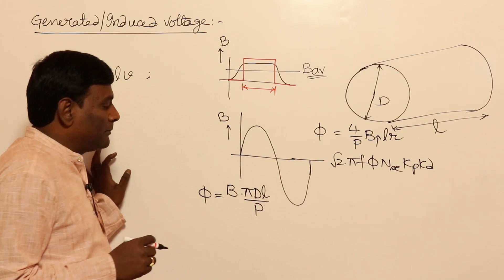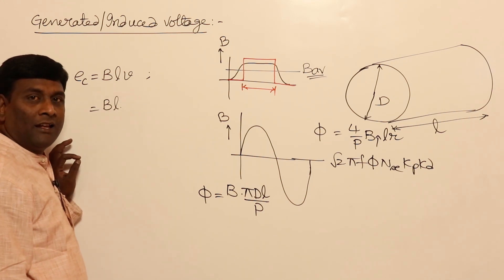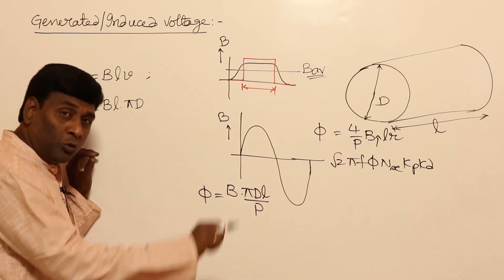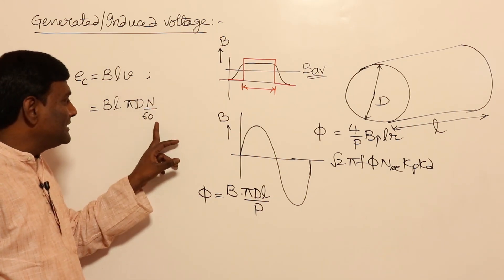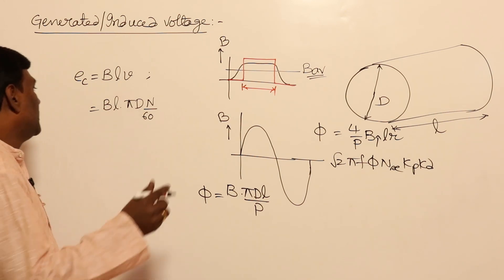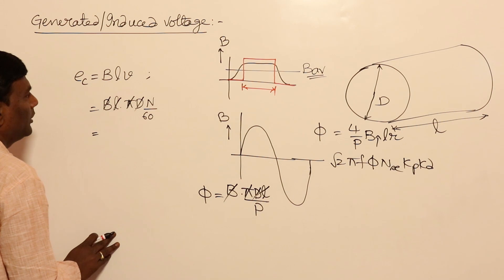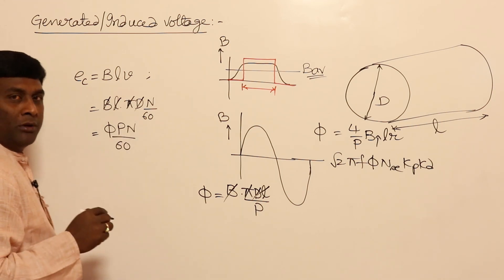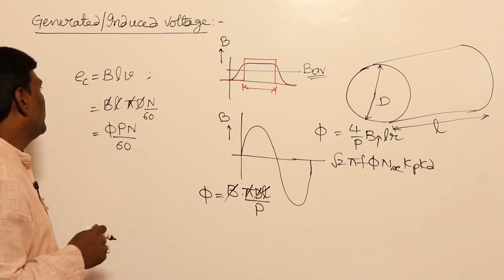What is induced voltage in a conductor? B into length into velocity — and in one revolution, how much will be the velocity? πD. πD is going to be the velocity because you are rotating the rotor. So velocity = πD * N/60. N is revolutions per minute; dividing by 60 gives revolutions per second. So substituting B, L, and v = πD*N/60, and replacing πDL/P with φ, this gives induced voltage per conductor = φPN/60.